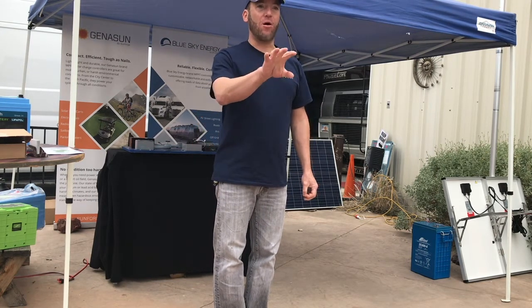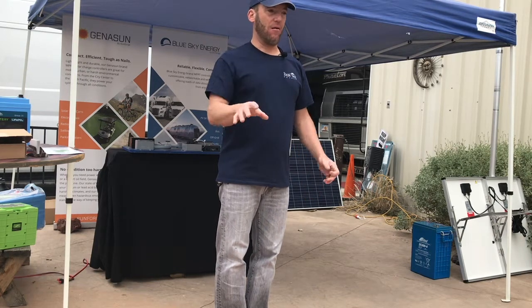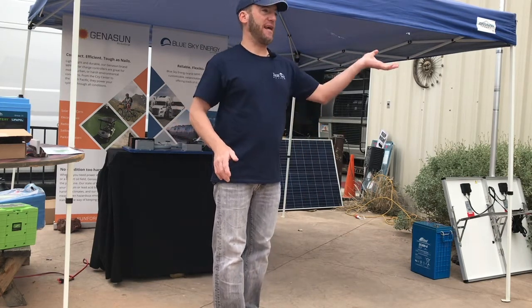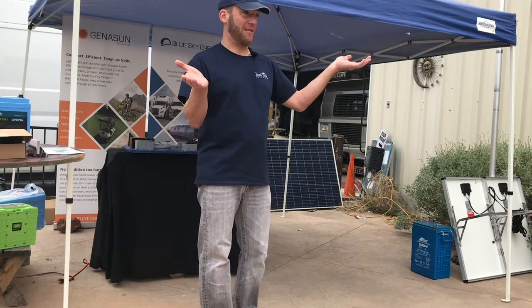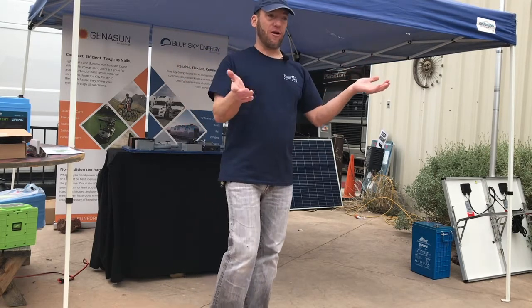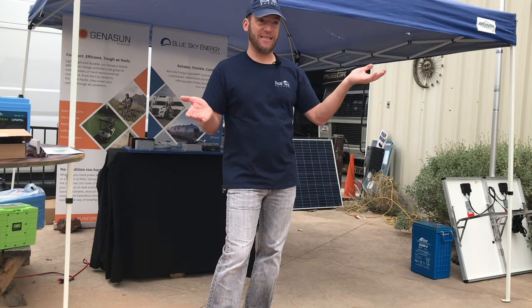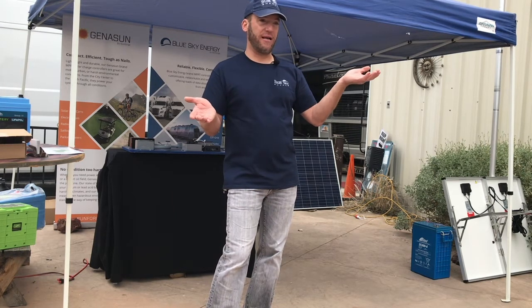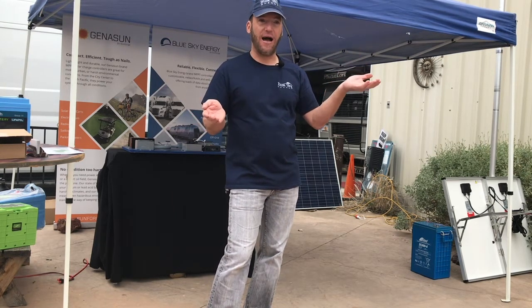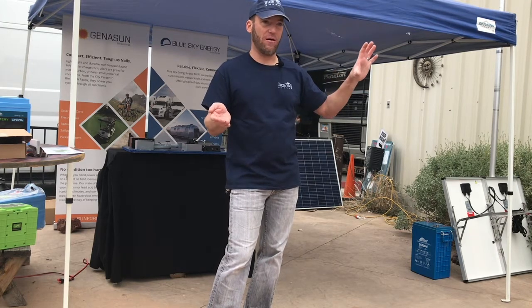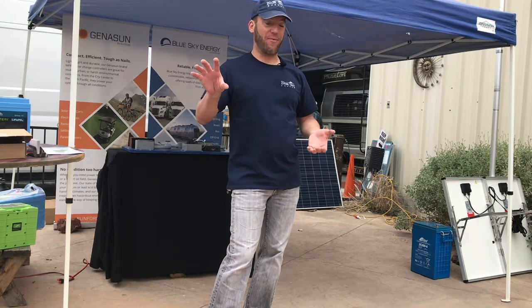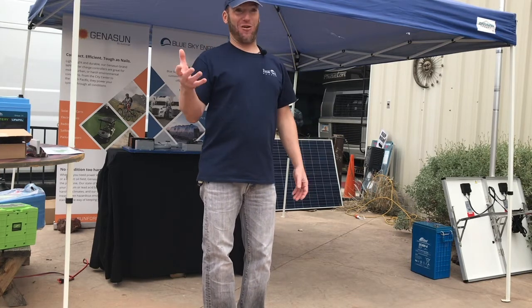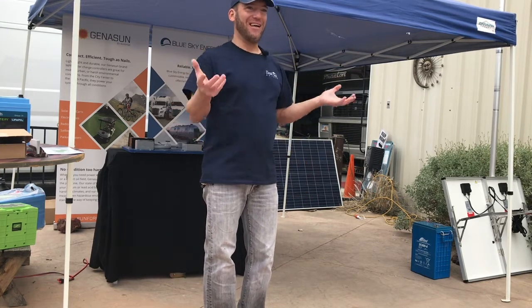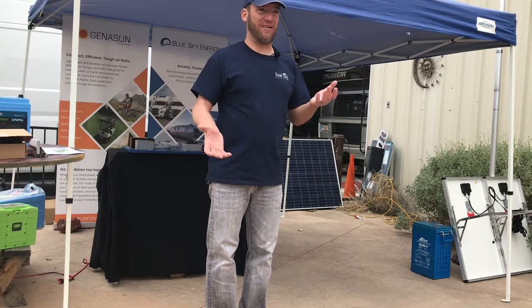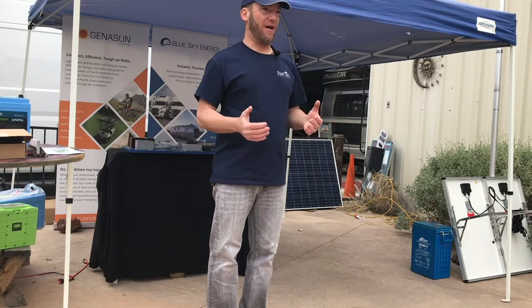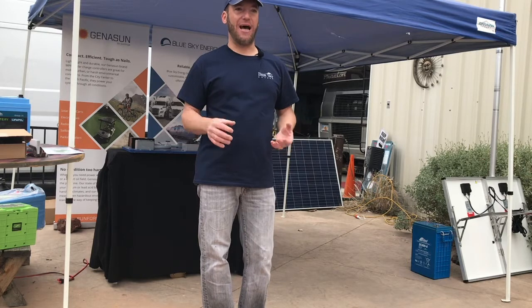But your battery voltage remains the same, right? So he's asking, what if this controller has 10 amps out and this one has 5 amps out? Well, again, the controller with 10 amps out has a little more resistance, so it might transition a little sooner because it observes a slightly higher voltage at the controller versus the batteries. But if the one with 5 amps out has larger wires—or smaller wires—then it might see it differently. So you play the resistance game between what the actual voltage is as observed at the charge controllers.